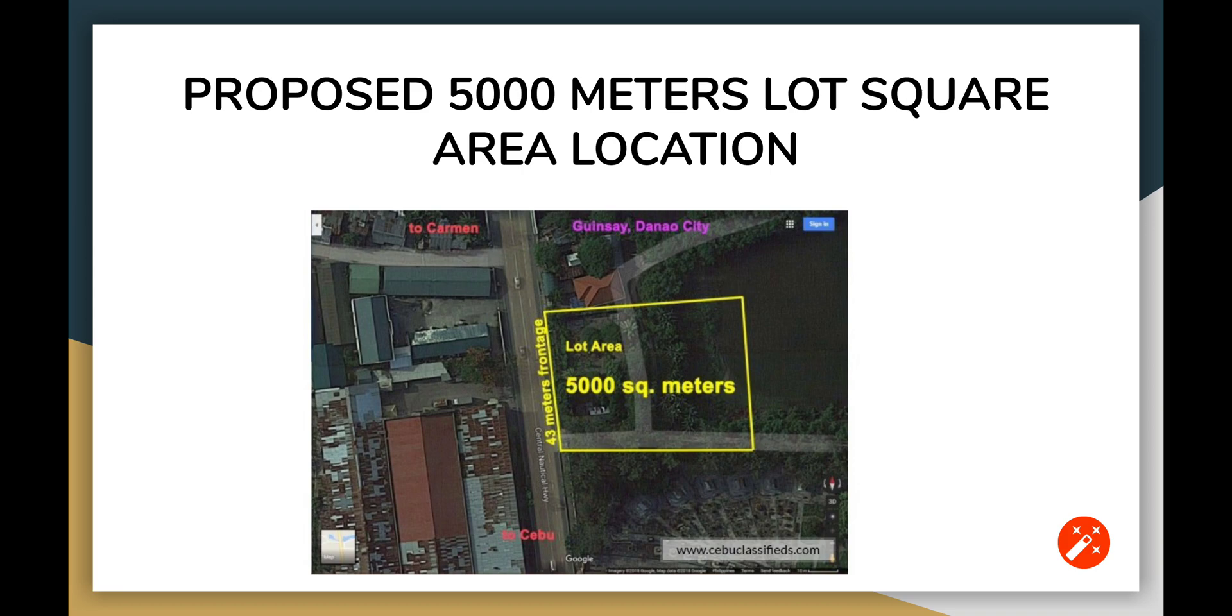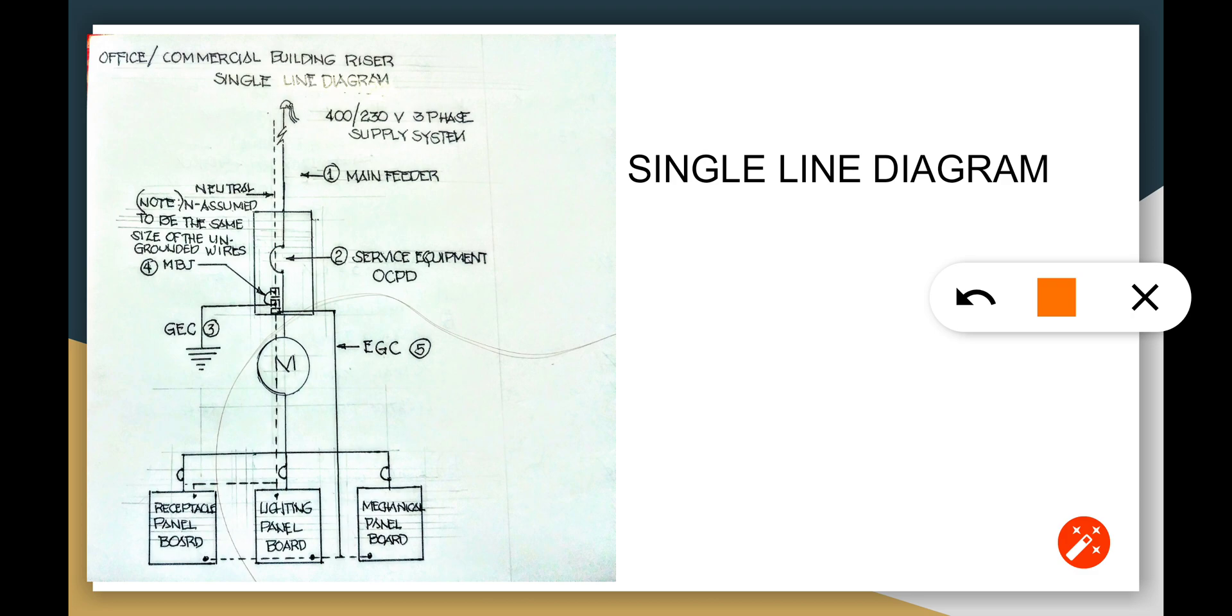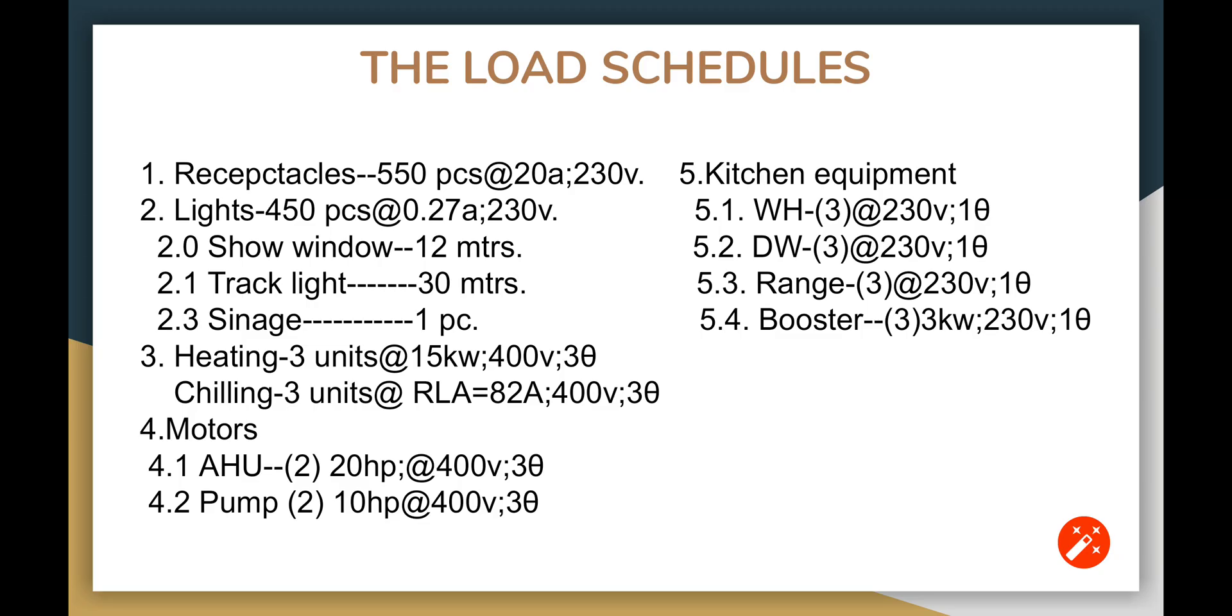It's going to be a proposed 5000 square meter area location with a single line diagram. We're going to find out the main feeder line, the service equipment OCPD, the equipment grounding conductor, the GEC, and the main bonding jumper. We're going to calculate everything and assume the neutral is going to be the same size as the ungrounded conductors for the purpose of mitigating expected harmonics in the system that distort the system. These are the load schedules.